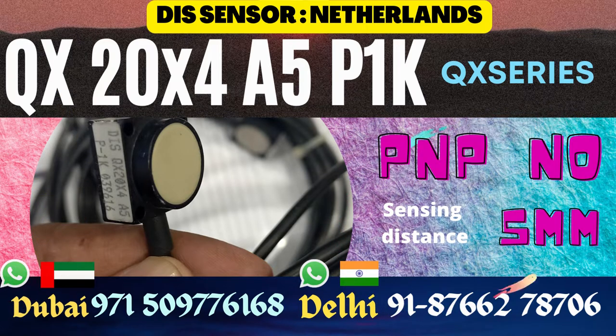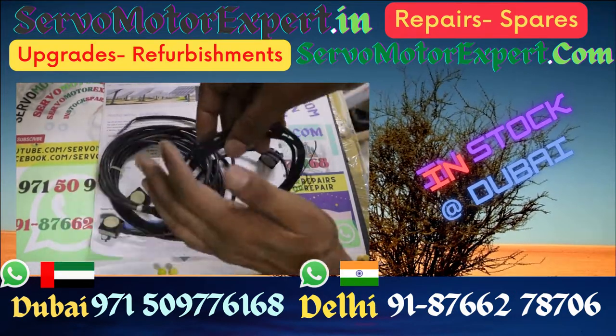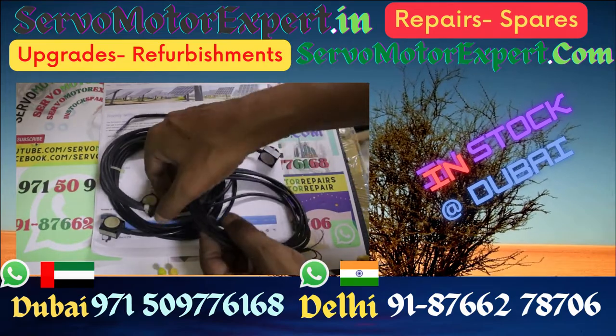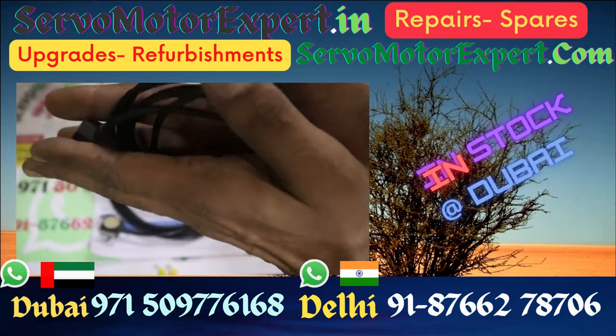The sensor you see here is Quadro 20, with an envelope of 20x20x12mm — square base 20 by 20 and height 12mm. You get a switching distance of 5mm. Three wires shielded, PNP NO, 10 to 30 volt DC.